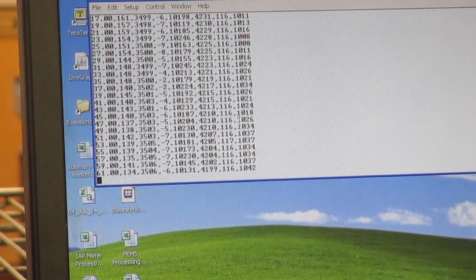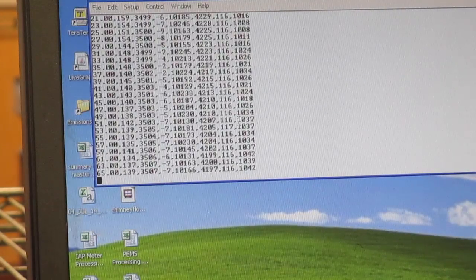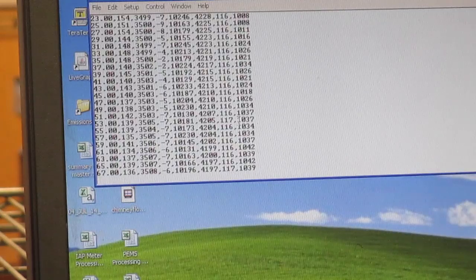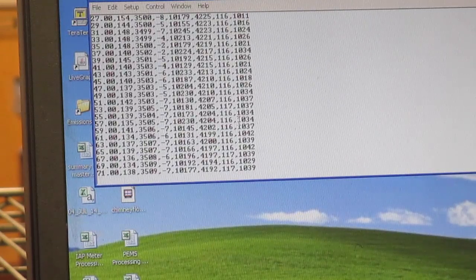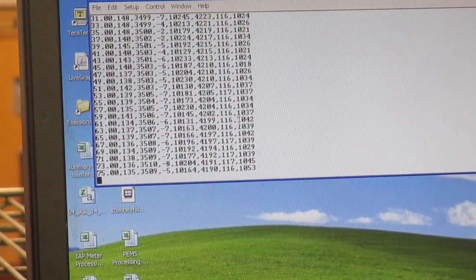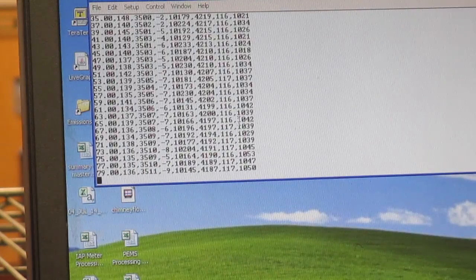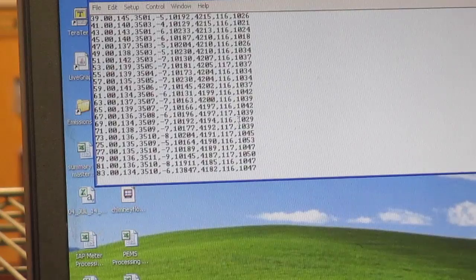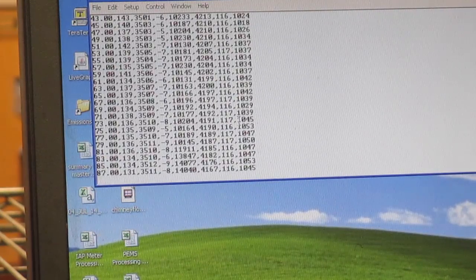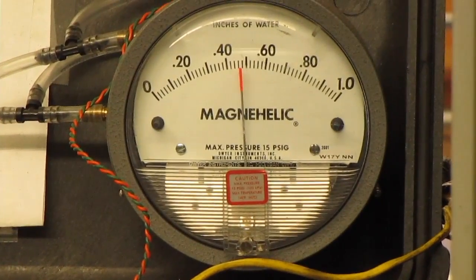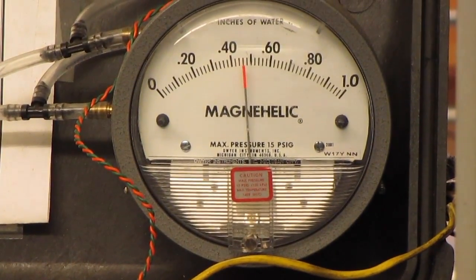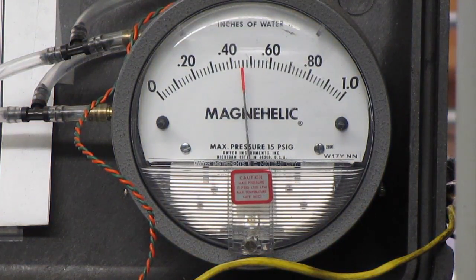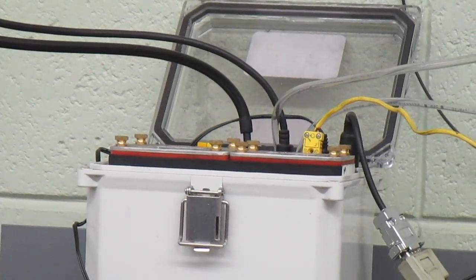And actually you can see, 1 minute has passed, but I said between 1 and 4 minutes, just the way it's written. So you can see in the first, second, third, fourth, the fifth column, that is the flow reading right now. So when I turn on the blower, flow reading went from 10,200 to about 14,000. Magnehelic was at 0, and now it's at about 0.47, maybe 0.46. Now, that's all great. If you get one of the new sensor boxes, which nobody has yet, then you won't have to do that.